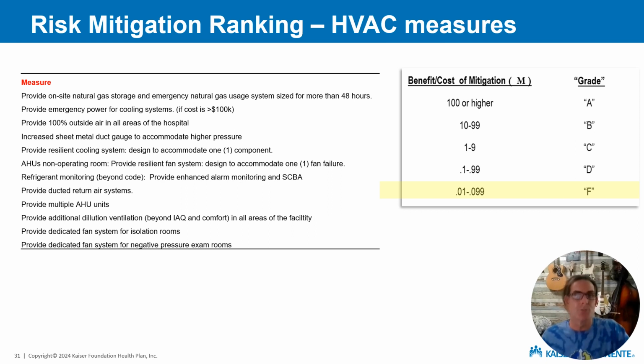Again, you'll notice there's some code requirements in this category, as well as some things that are very commonly applied on hospital projects, right? On-site natural gas for 48 hours, emergency power for cooling systems, resilient fans with N+1, fan walls, very common in our designs, not a great investment. Ducted return systems, very expensive, very common in our designs. It's a code requirement, not a great investment.